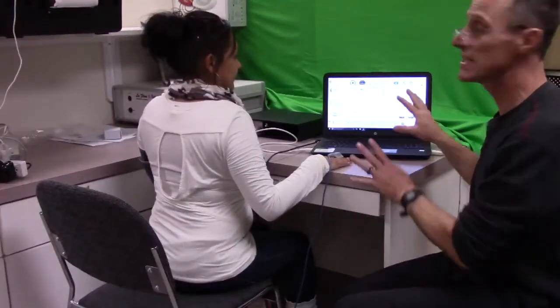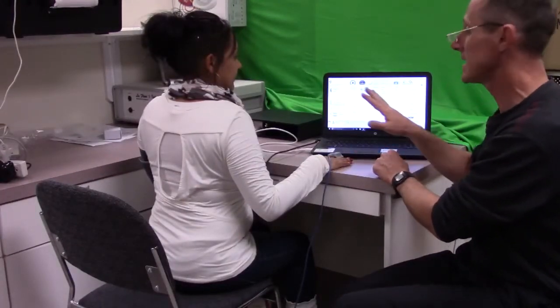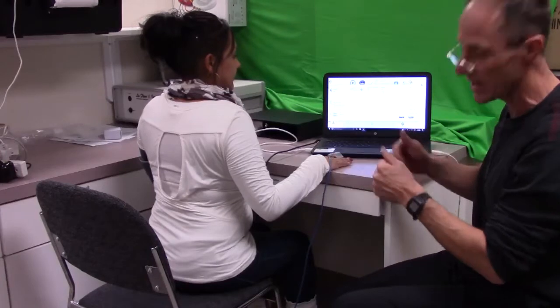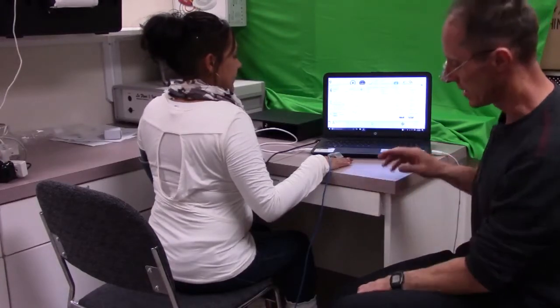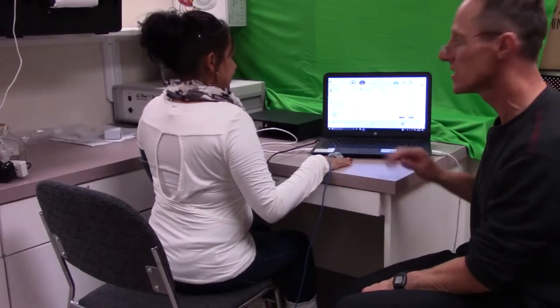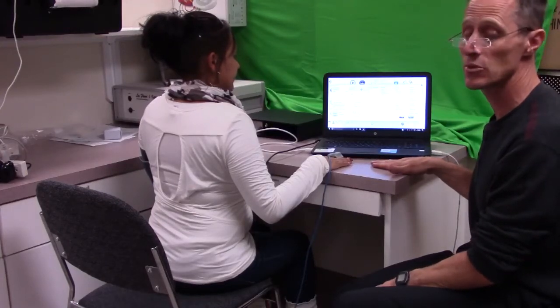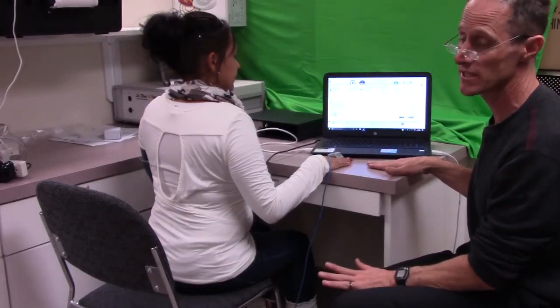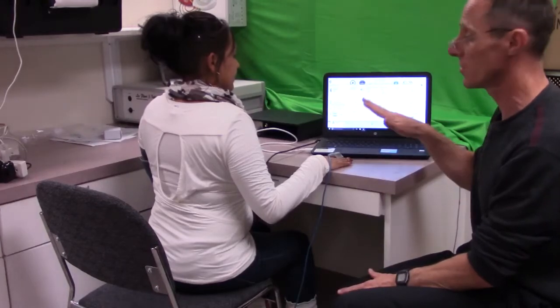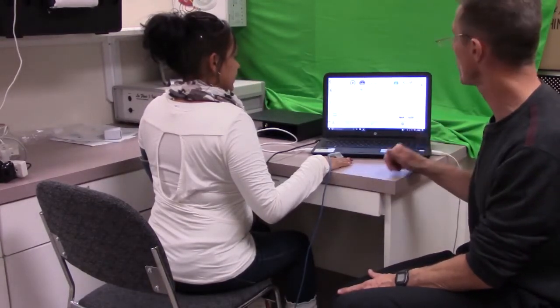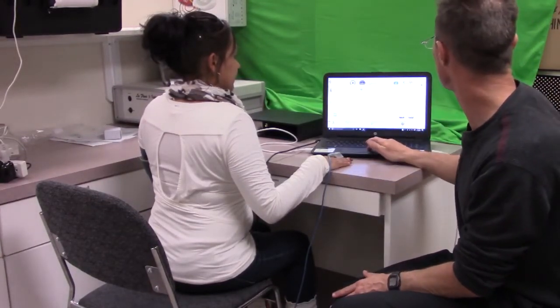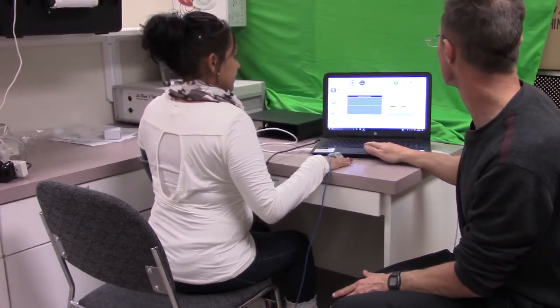Okay, so now we've entered the information, and we're making sure that our patient is sitting upright, but relaxed, with their feet on the foot plates. We want to make sure we tell the patient that we do not want them to speak during the test. So during the test, they need to remain still with no verbal communication. At this point, I'm going to go ahead and hit OK, and I'm going to start my test.